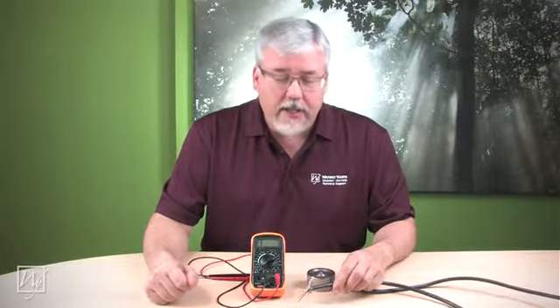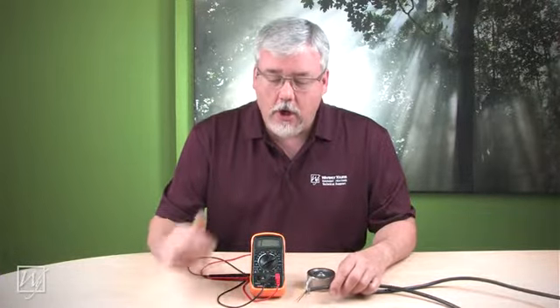So that wraps up today's tech tip on how to test the slab SS sensor for your SCE 120 controller. It's a very simple thing to do. All you need is a digital ohmmeter and the end of the wire and you're set to test your slab SS.